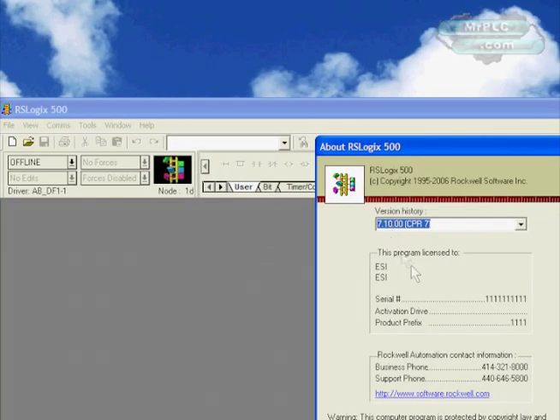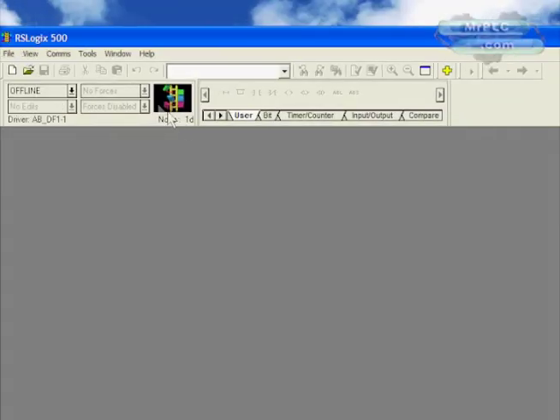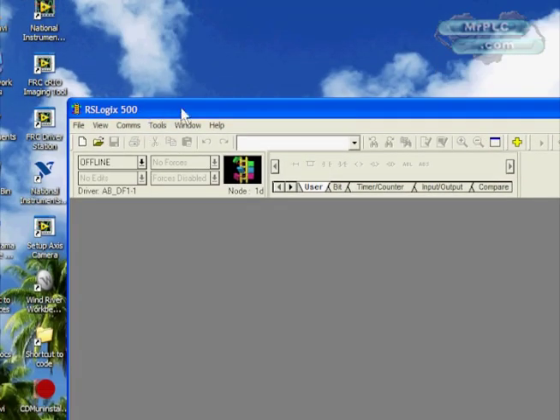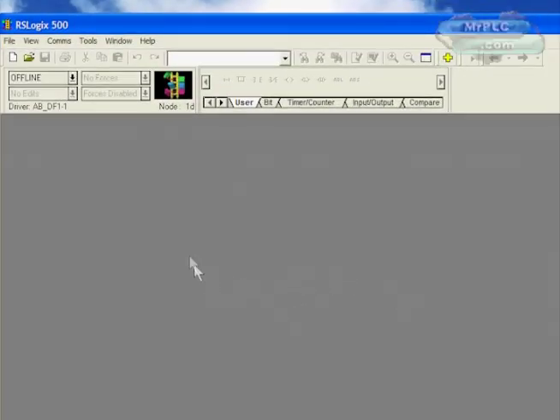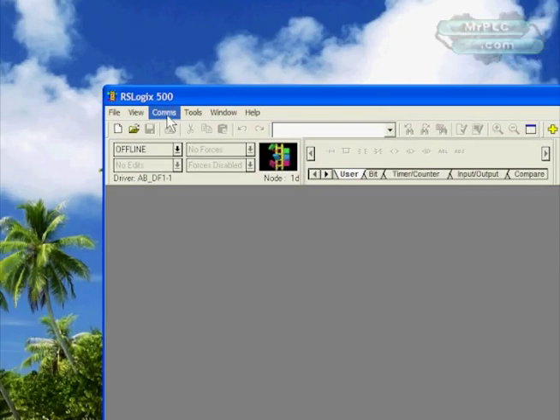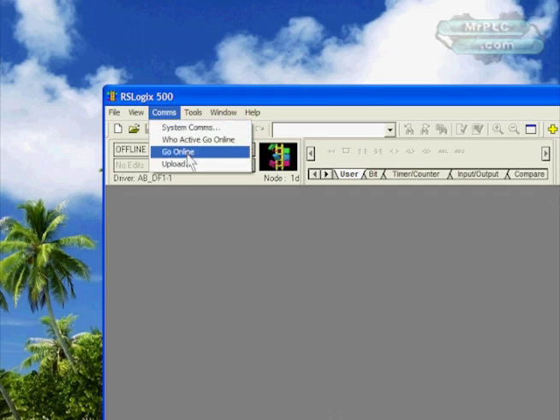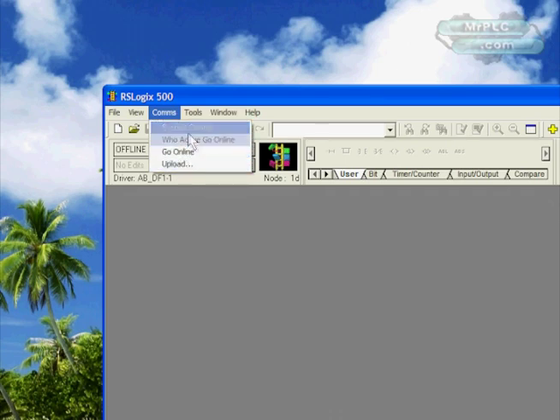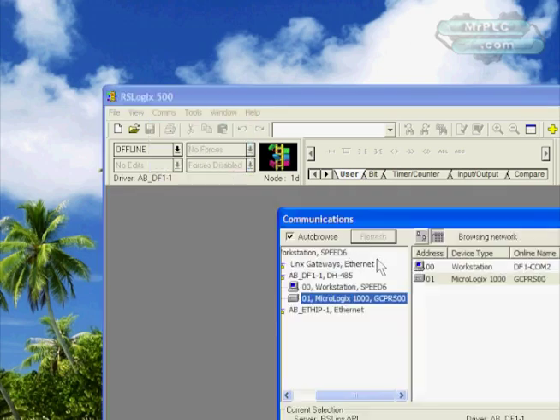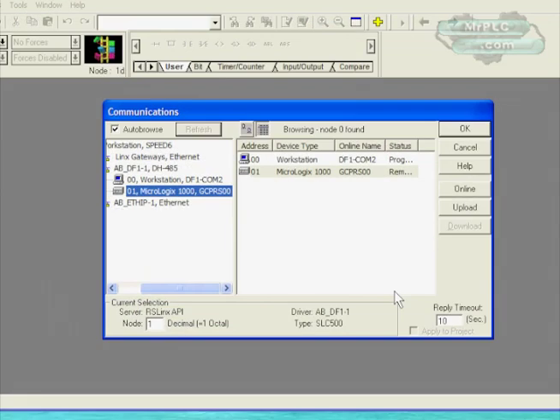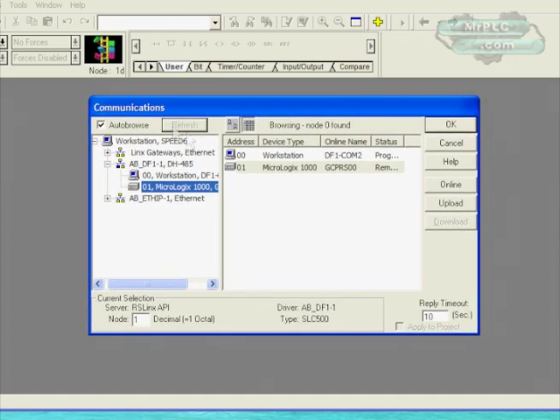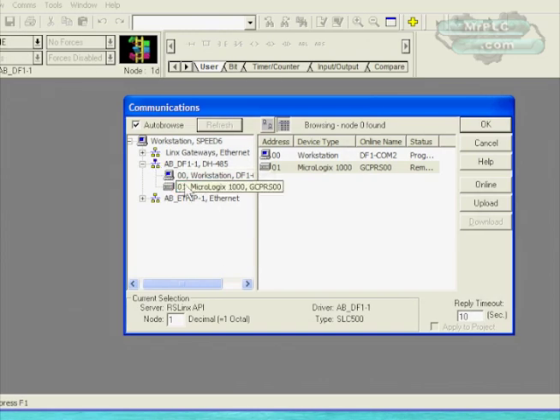Now we're ready to start our programming software. In this case it's going to be Logix 500, and I'm using the free version of Logix 500, which is version 7.1. There's actually a new version out there, version 8. In order to get Logix to communicate, I like to go to Comms, System Comms. Some people do the online upload thing and I think sometimes that causes issues, but I found that if I always go to Comms, System Comms, I have a good success rate.